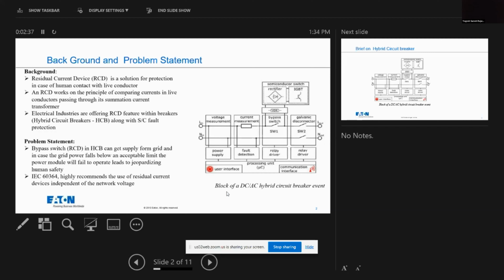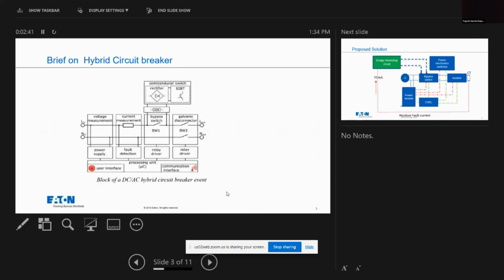I will go to the next slide now. I'll briefly describe what exactly the hybrid circuit breaker is, and then I will explain my proposed solution. This is the very high level block diagram of my DC or AC hybrid circuit breaker. There is a first block of voltage measurement supplied by live and neutral, and then a current measurement. These two are needed to make a decision during this operation. The third block is the bypass switch, which continuously monitors the current and voltage. If an arc is there, this bypass switch is enabled using the microcontroller. Then the galvanic disconnector is the main contact driven by the relay driver, and it will give isolation. So this is a brief block diagram of the hybrid circuit breaker cell.